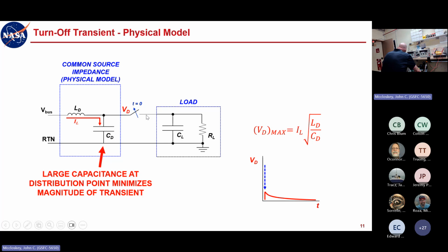In fact, I think the first time I heard about these kind of transients was in the context of a fuse blowing. And then it turned out we already were applying CS06, and okay, we don't really need a separate requirement saying you shall survive a fuse blow that produces this kind of transient on the bus with these characteristics. We've already got CS06 that encompasses that. We're good with that. We don't need a separate requirement that says the same thing. So does that answer your question, Mike?